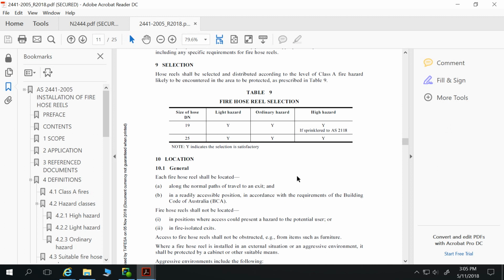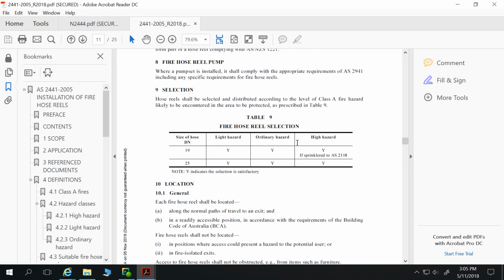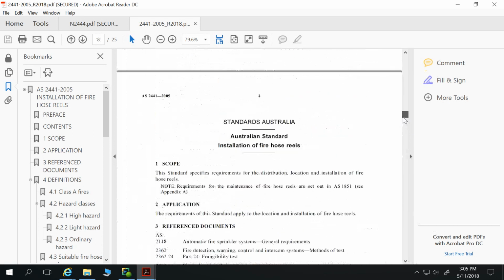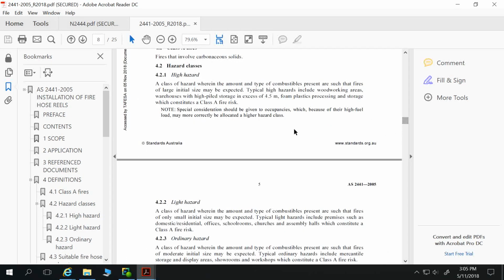But anyhow, that leads us to think, okay, what are these different hazards? So, head back up to our definitions. Got hazard classes. So high hazard, a class of hazard wherein the amount and type of combustibles present are such that fires of large initial size may be expected. Typical high hazards include woodworking areas, warehouses with high piled storage in excess of 4.5 metres, foam, plastics, processing and storage which constitutes a Class A fire risk. And we'll cover that Class A fire risk a little bit later on. But that doesn't really sound like what we're doing, does it? We're not manufacturing pallets and mattresses and things like that.